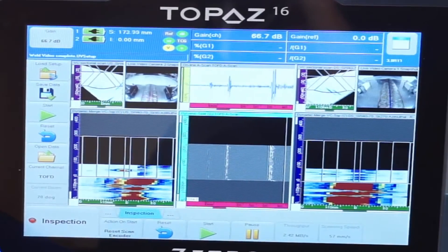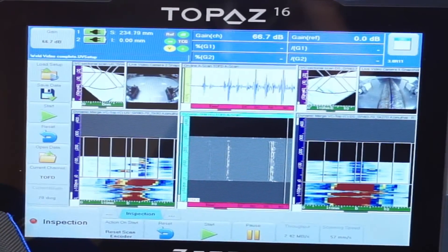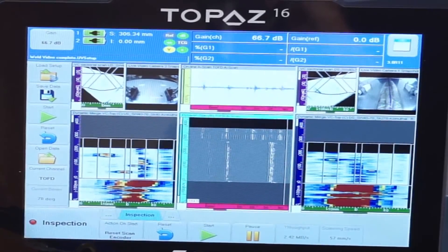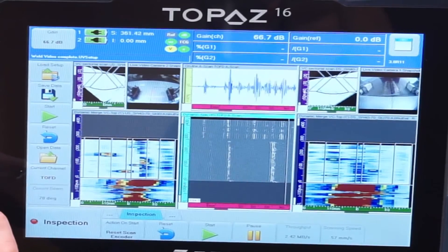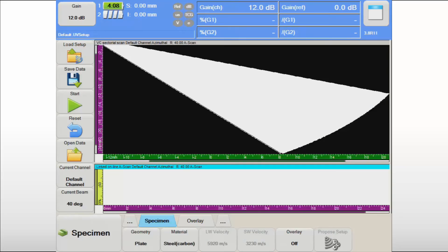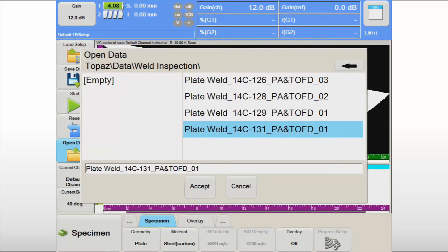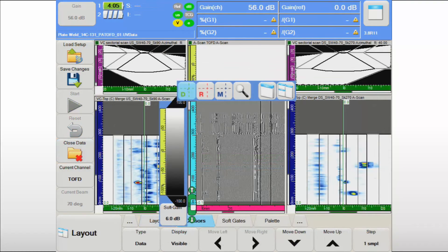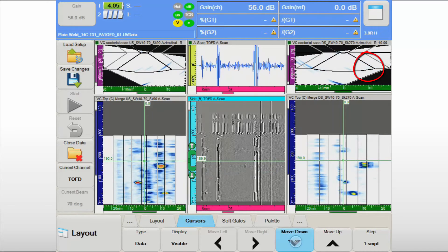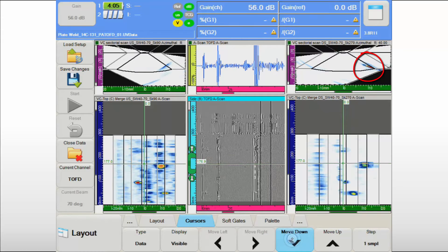The onboard 120 GB solid state drive allows for storage of more than 100 such inspection data files, therefore eliminating the need for time-consuming data transfer during the work shift. Previously recorded data files can be easily retrieved using the intuitive UltraVision Touch interface. By moving the data cursor, the data analyst can scroll through the inspection data to validate the quality of the recording and to identify critical regions. To perform the detailed evaluation of the indications, the data analyst can load dedicated layouts optimized for each inspection technique.